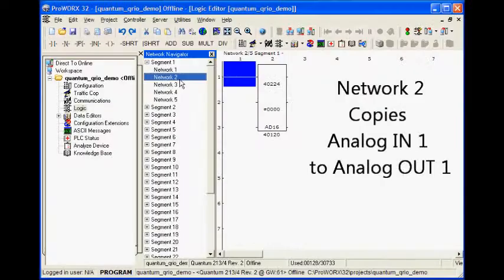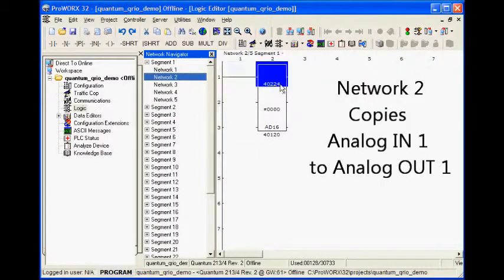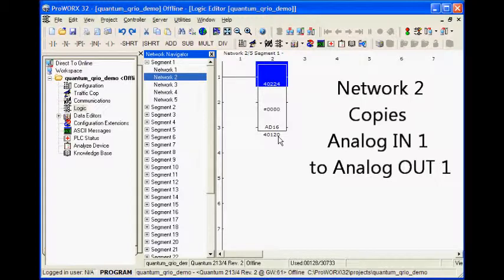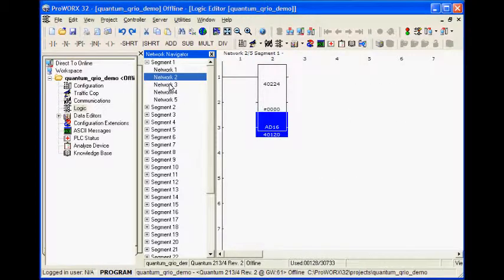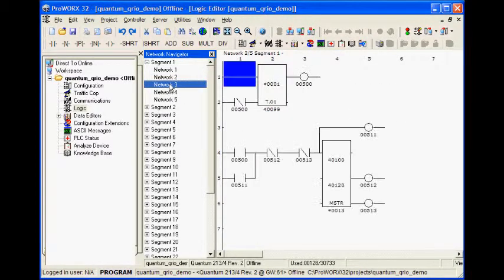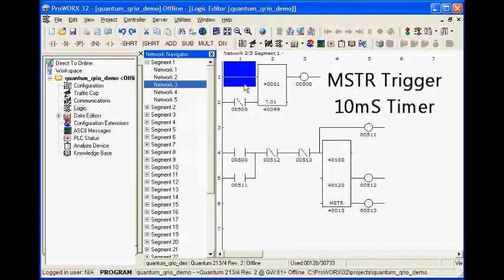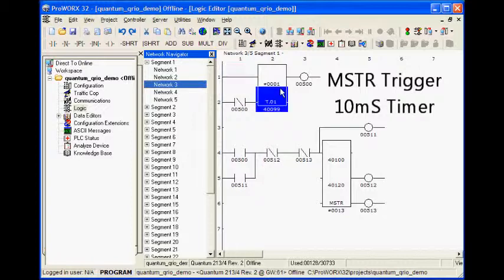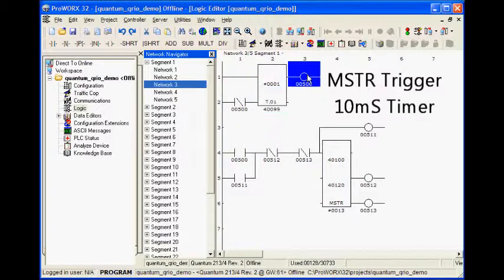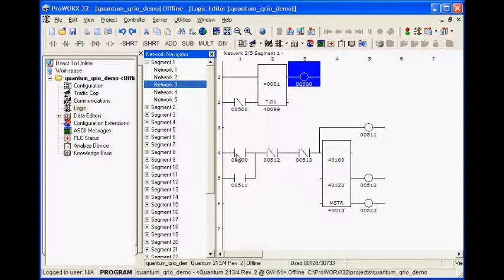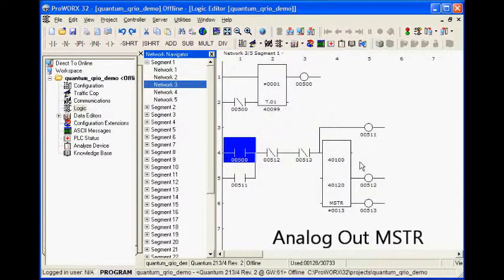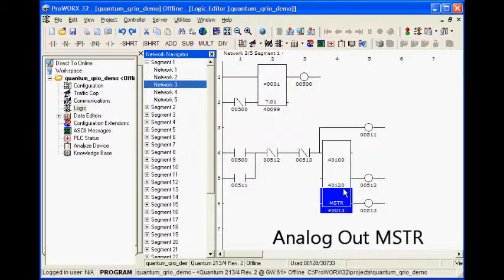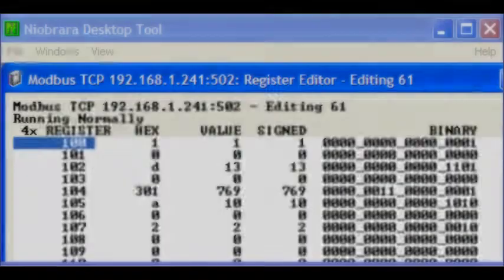The rest of the logic is for the analog inputs and outputs. Network 2 simply copies the analog input 1 to analog output 1. MSTR blocks must be used to configure and control the analog I/O. A timer is used to trigger the MSTRs which read and write the analog I/O. Each MSTR is latched on until it is successful or ends with an error.